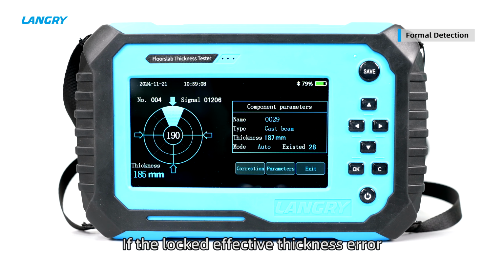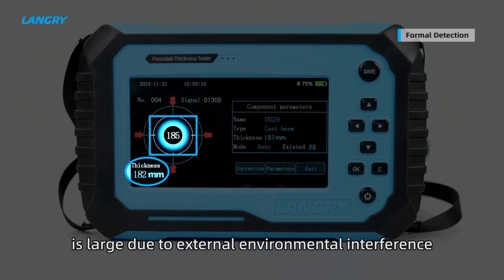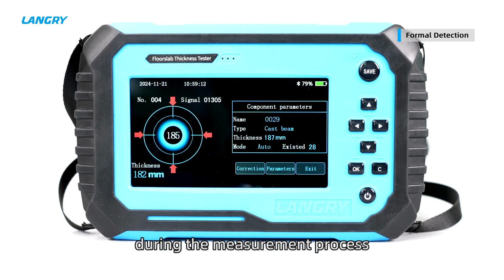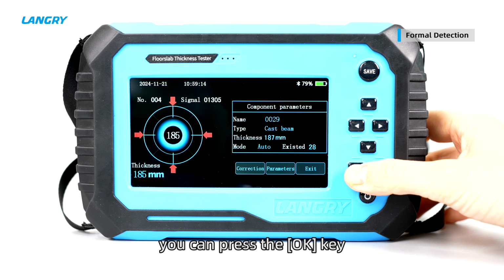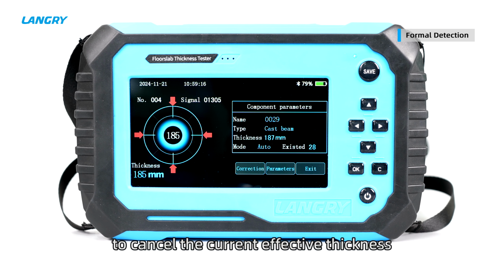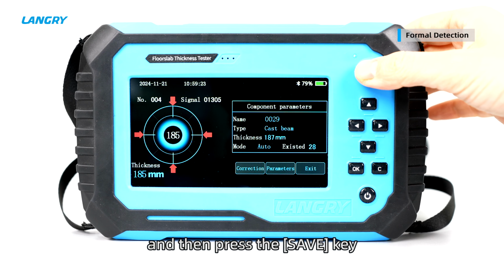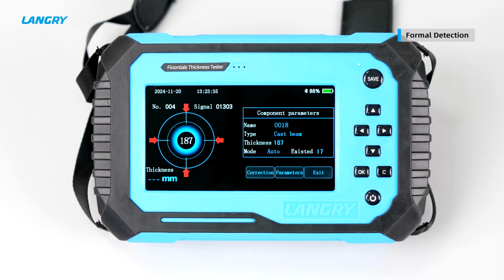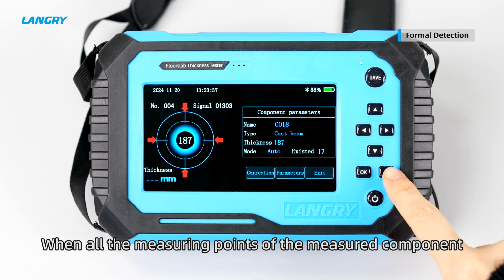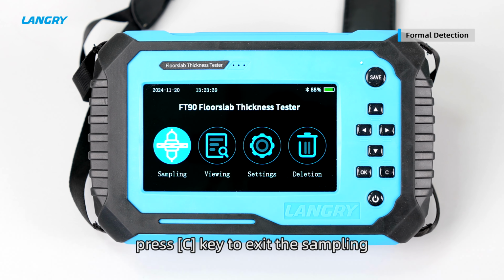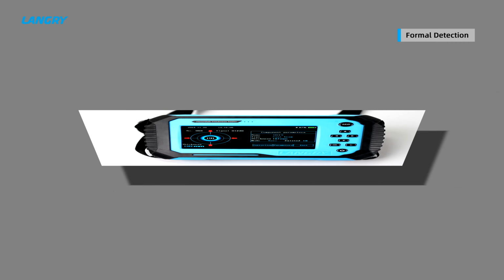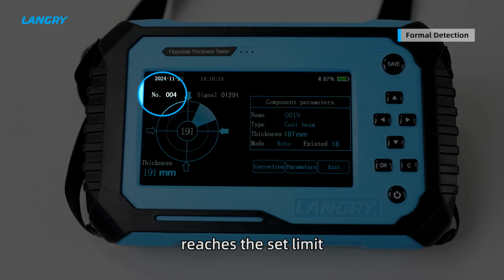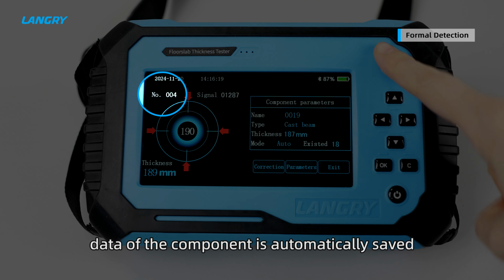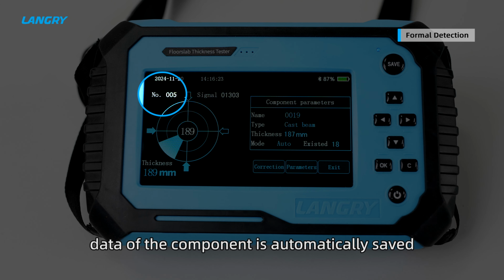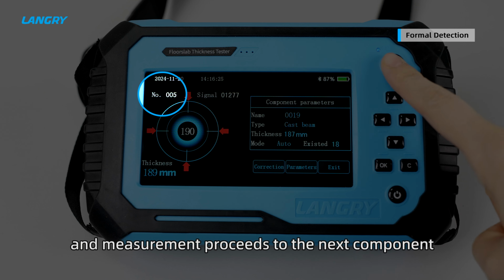If the locked effective thickness error is large due to external environmental interference during the measurement process, you can press the OK key to cancel the current effective thickness, and then press the Save key. When all the measuring points of the measured component are measured, press the C key to exit the sampling. When the number of stored points reaches the set limit, data of the component is automatically saved, and measurement proceeds to the next component.